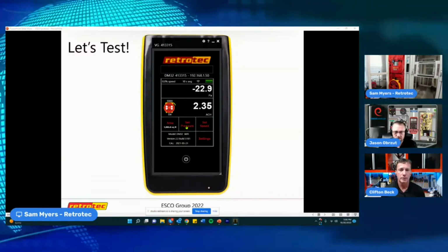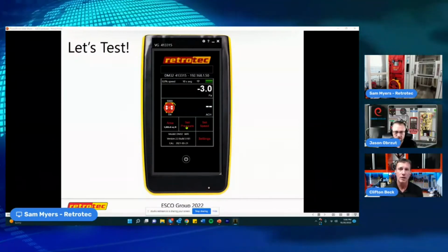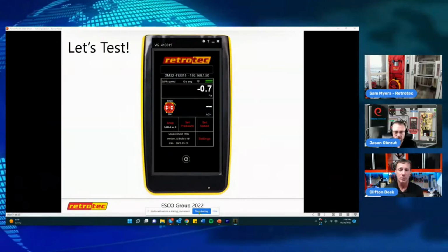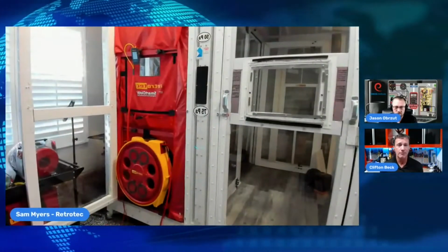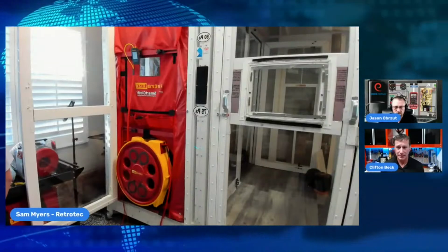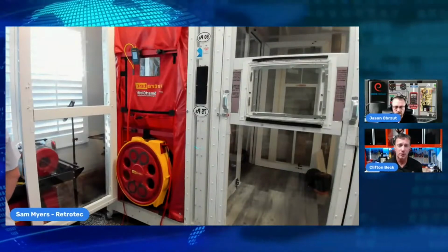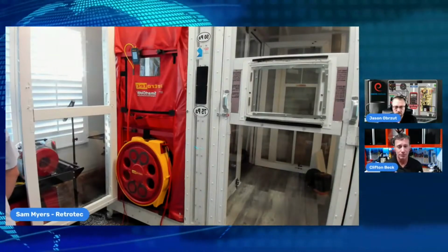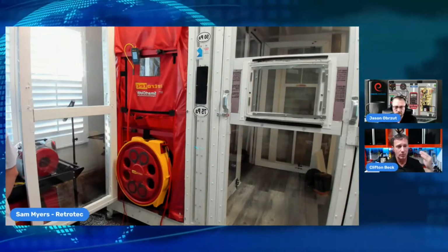Which brings up a point that we were kind of discussing earlier, Sam. We'll use it as one of our examples today. One of the forefronts of doing blower door testing is the state of Florida. And in the state of Florida, we're looking at specifications between 3 and 7. So below 7 is acceptable. Anything below 3 is going to require outside air to compensate for that. So in that instance, we can't have too tight of a structure once we get below 3.